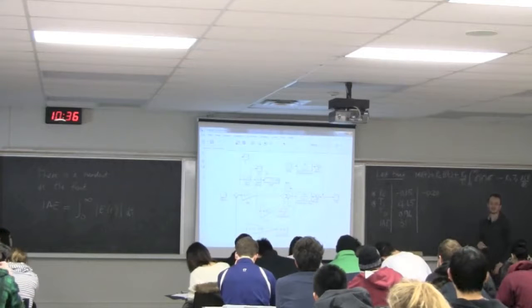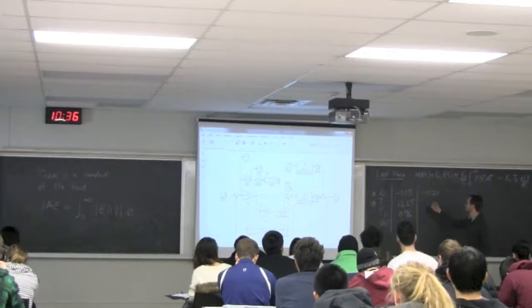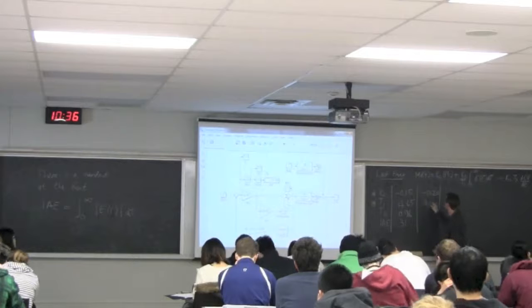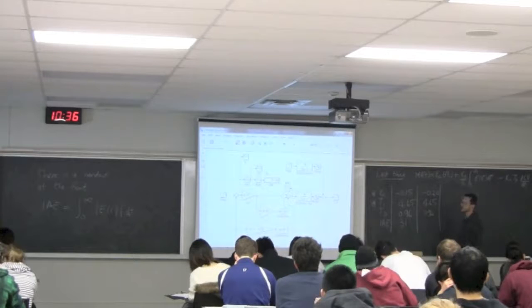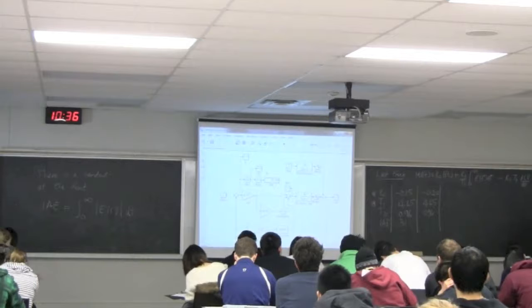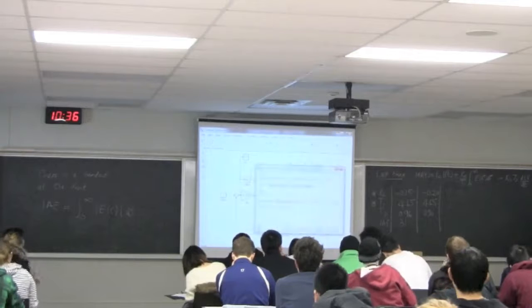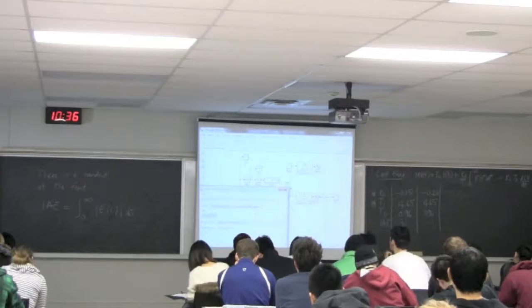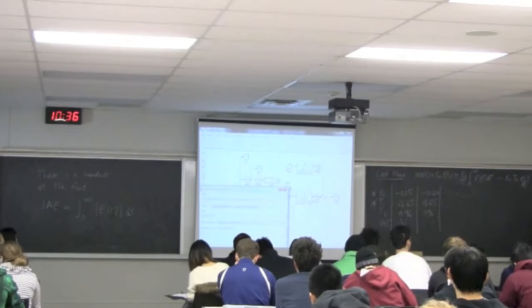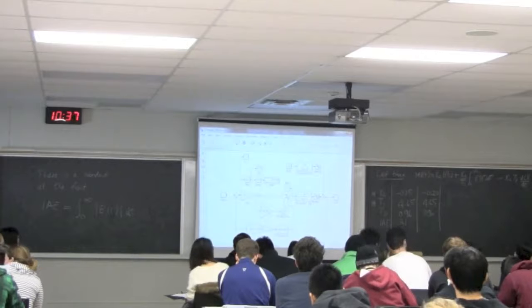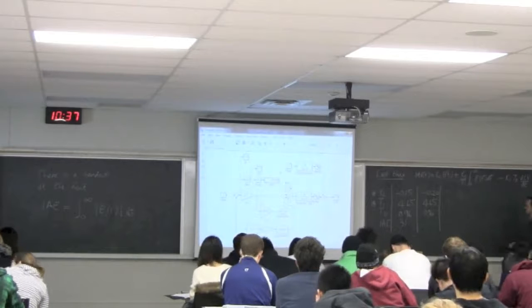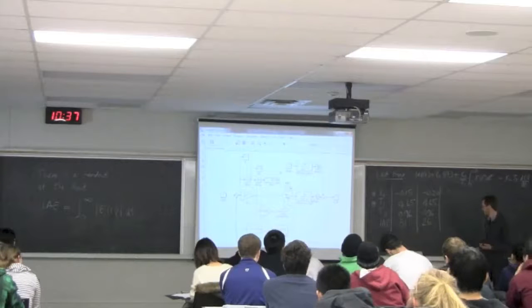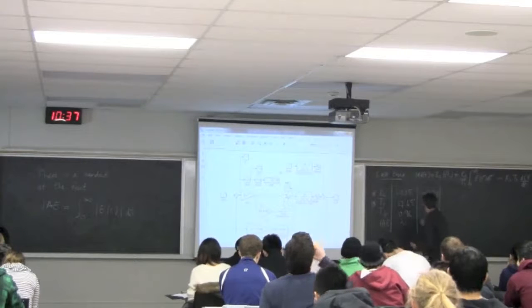We increase it in terms of magnitude. So if we find something a little more aggressive, minus 0.2. So I'll go greater in magnitude. The sign is always going to stay the same. Let's go a little bit more aggressive. Leave TI at 4.65. Leave TD at 0.96. And we showed last time that if we do that, minus 0.2, then we got an IAE of 26 units. So this is actually better tuning. So this is my best tuning so far.